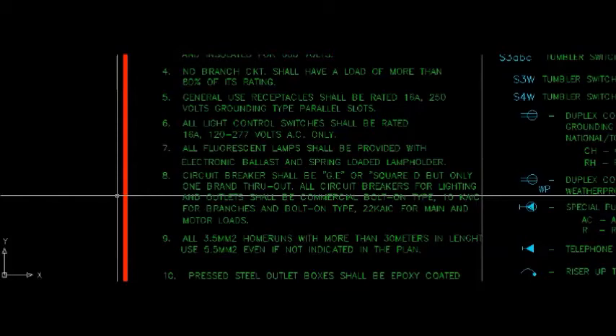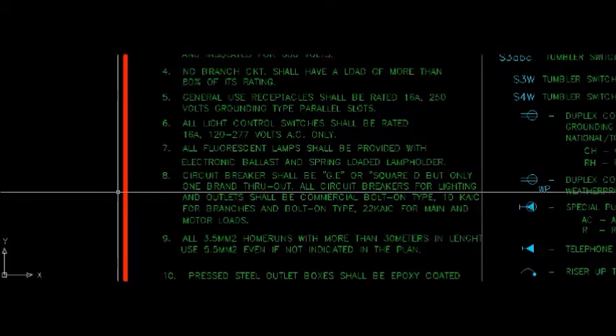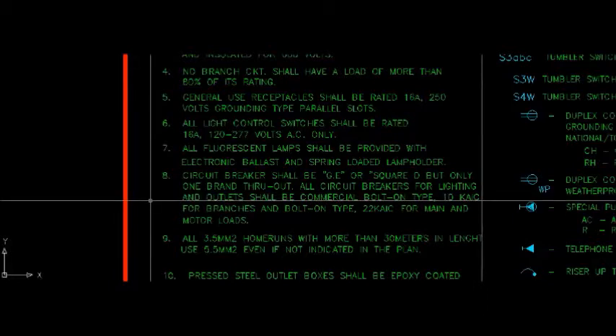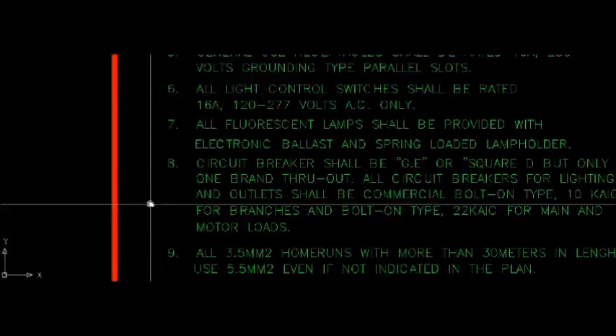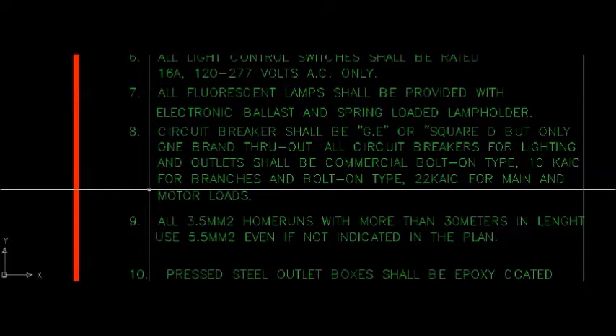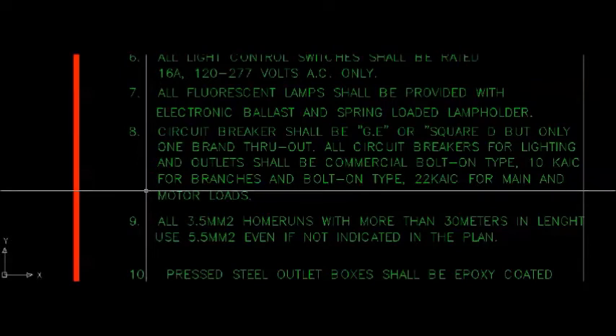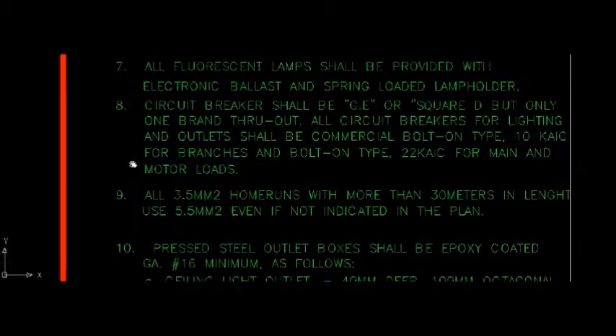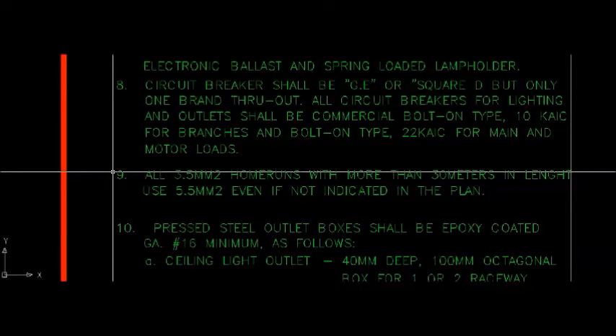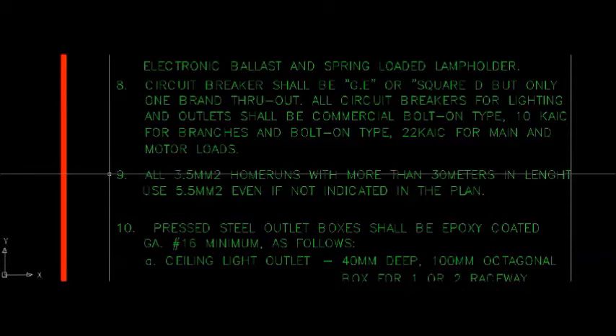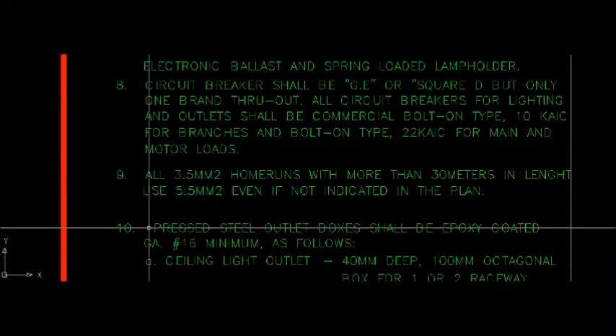General use receptacle shall be rated 16 amperes, 250 volts, grounding type, parallel slots. All light control switches shall be rated 16 amperes, 120 to 277 volts AC only. All fluorescent lamps shall be provided with electronic ballast and spring-loaded lamp holder. Circuit breaker shall be GE or Square D but only one brand throughout. All circuit breakers for lighting and outlets shall be commercial bolt-on type, 10 KAIC for branches, and bolt-on type, 22 KAIC for main and motor loads.